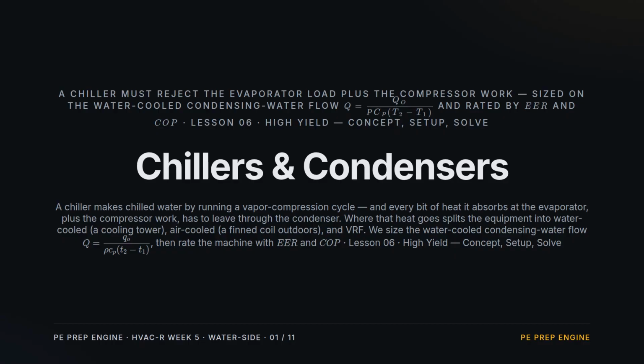Week 5, Lesson 6, Chillers and Condensers. A chiller makes chilled water, and everything it pulls out of that water, plus the work the compressor adds, has to be rejected at the condenser. How you reject it, to a cooling tower, to outdoor air, or through a VRF system, sets the machine's efficiency. We'll size the condensing water flow for a water-cooled condenser, then rate a machine with EER and COP.